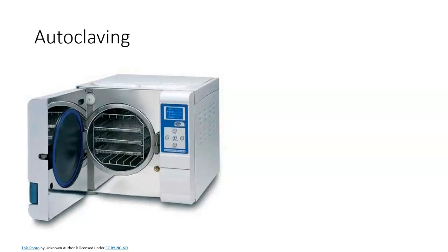An autoclave provides moist heat under pressure. Under atmospheric pressure, steam is 100 degrees Celsius. That's the boiling point of water. In an autoclave, that steam is pumped into an enclosed chamber that allows for the pressure to build up, and that raises the effective temperature of the steam.